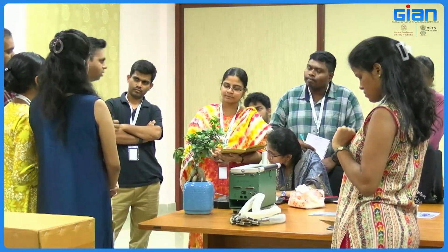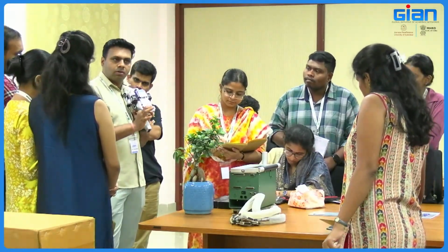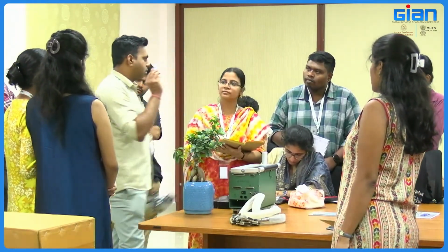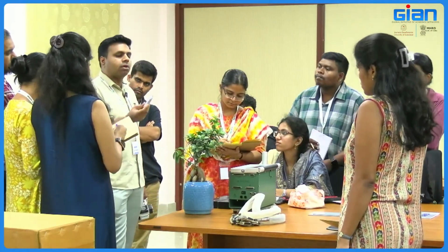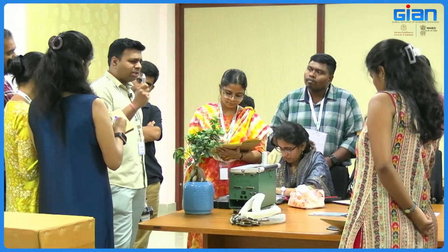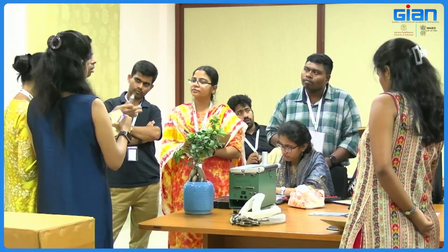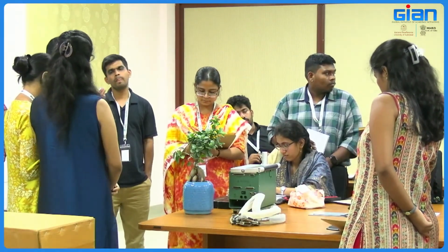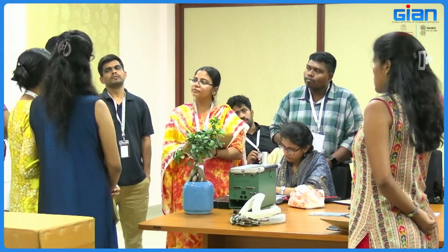That is the internal CO2 concentration. Another thing you need to do: one of these two is for reference CO2, one is for sample CO2. Now how do we supply CO2? We supply CO2 with cylinders. We use these CO2 cylinders to supply the reference CO2 concentrations. Why do we use these 12 gram CO2 cylinders? Usually it will last for 9 to 10 hours, then you have to discard. Whether you do the experiment or not, the CO2 will be released. Once it is punctured, it has to be used in one go. So if you want to repeat the experiment tomorrow, you have to use a fresh CO2 can.